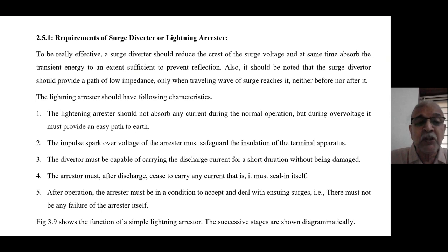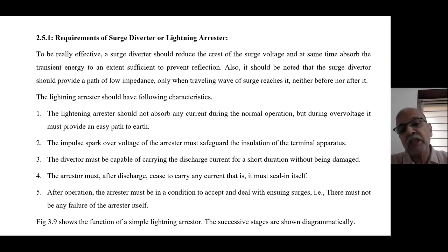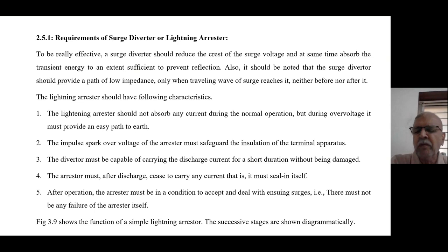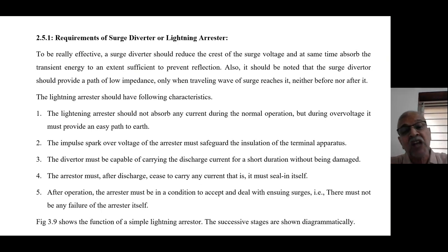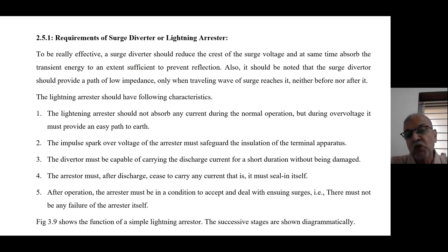The second requirement: the impulse spark-over voltage — the value at which the arrester sparks over and grounds the current — must safeguard the insulation of the terminal apparatus, meaning all transformers, CT, PT, etc. Third requirement: the diverter must be capable of carrying the discharge current for a short duration of time, because it is carrying current of the order of 10,000 amperes. The total lightning activity is complete within one millisecond, but for that short time it must carry that current without being damaged.